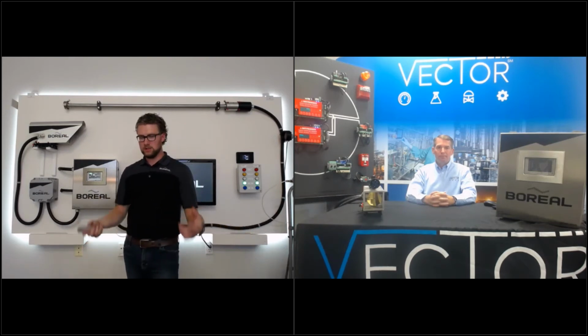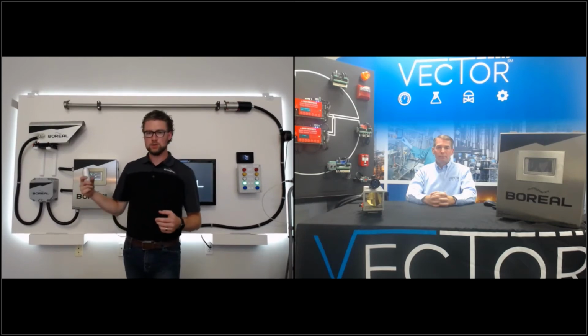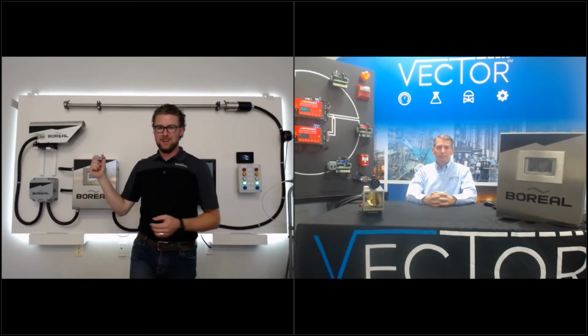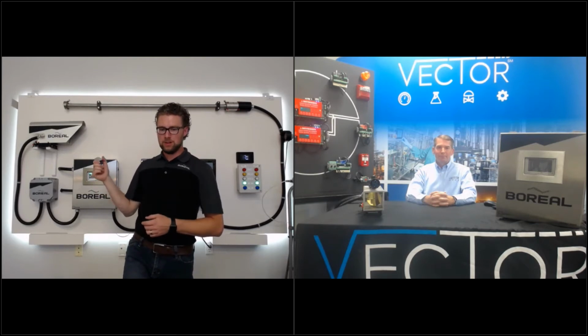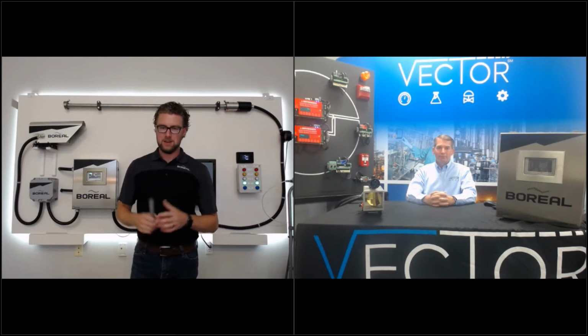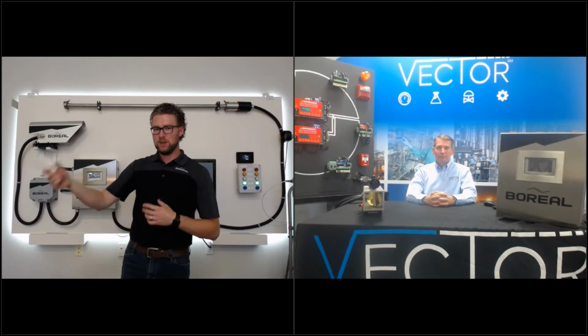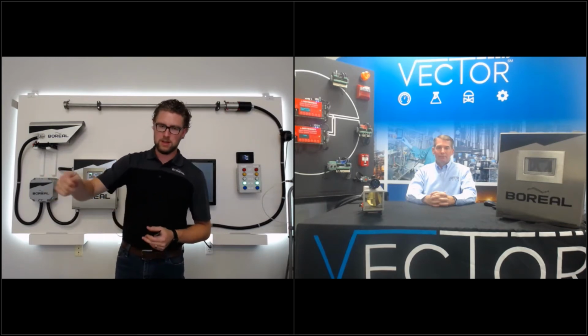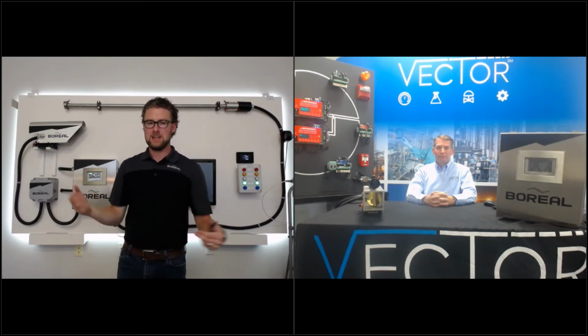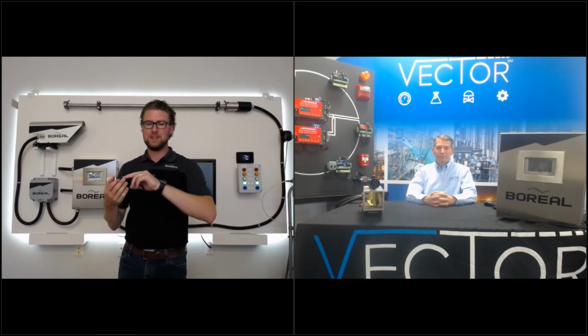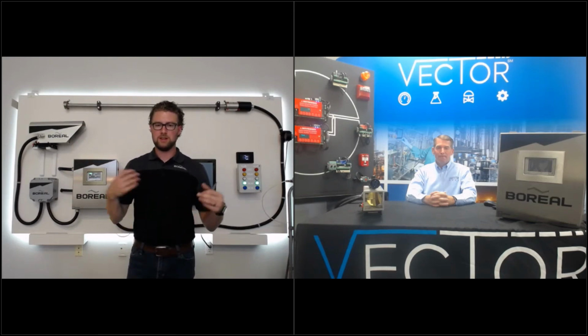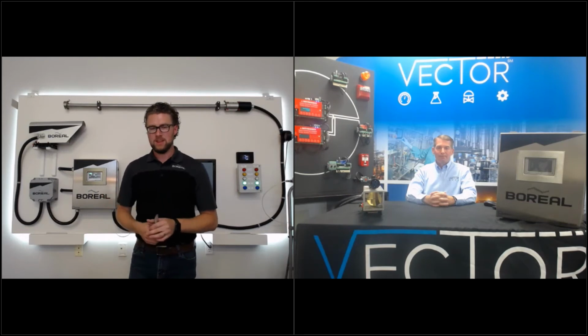Another good example on this leak detection and repair application is the fact that we've had customers pay their systems off in a week by just finding small incipient little leaks coming out of packings of valves. Once they find those small leaks, they go with the wrench, tighten up the packing, and that saves the cost of the valve, the time, and the downtime associated, particularly if there's no maintenance or bypass loop in there.